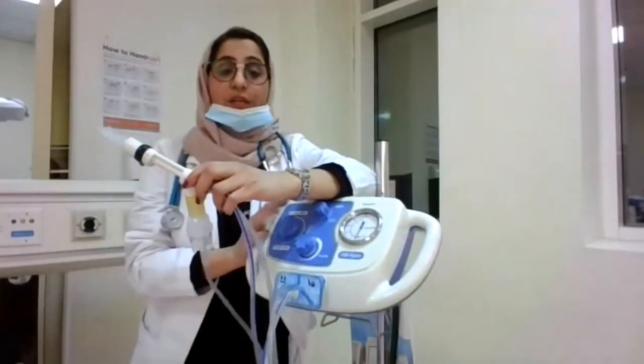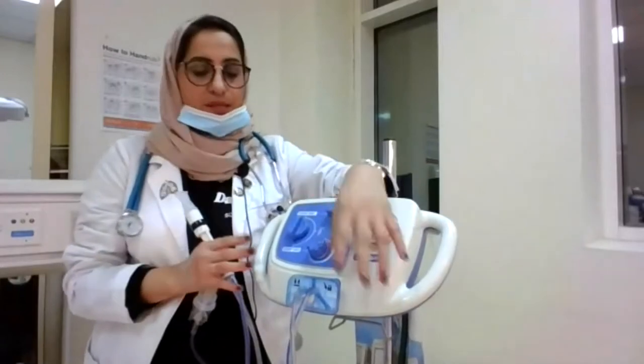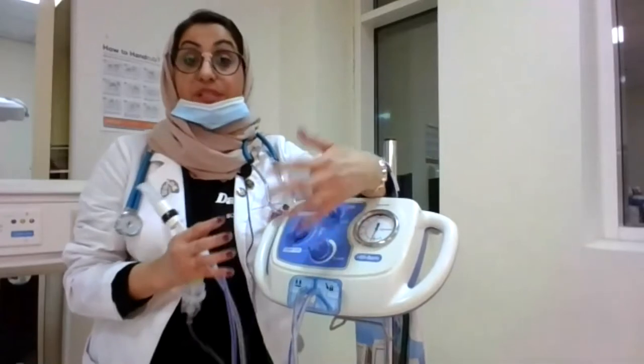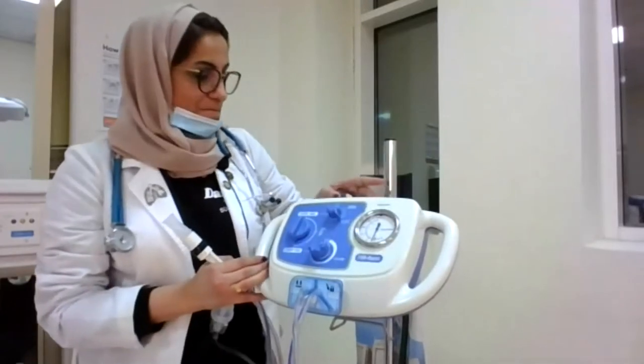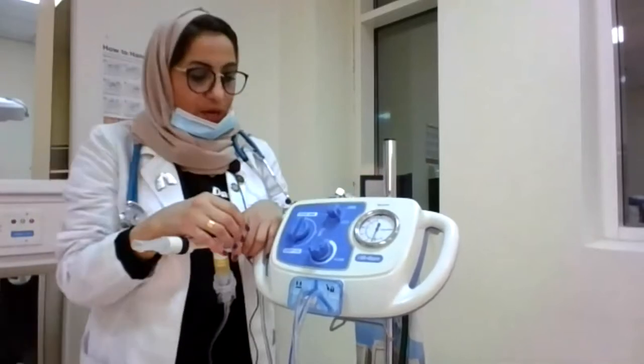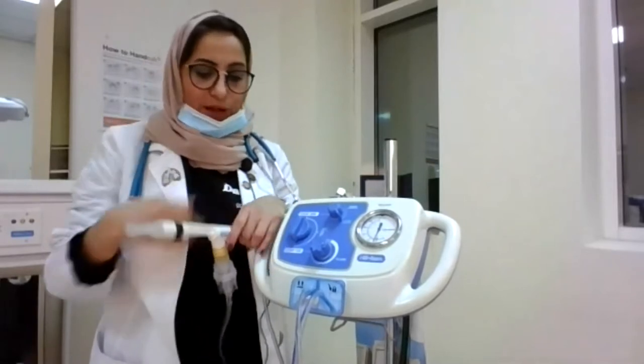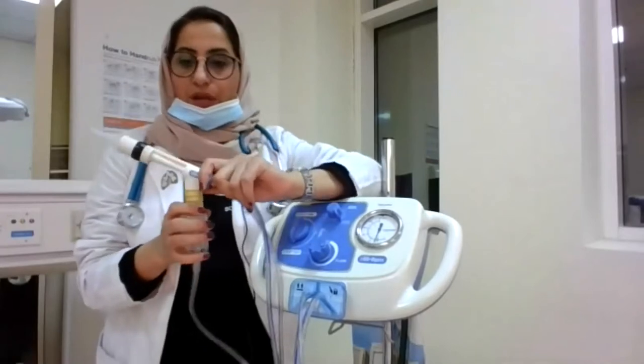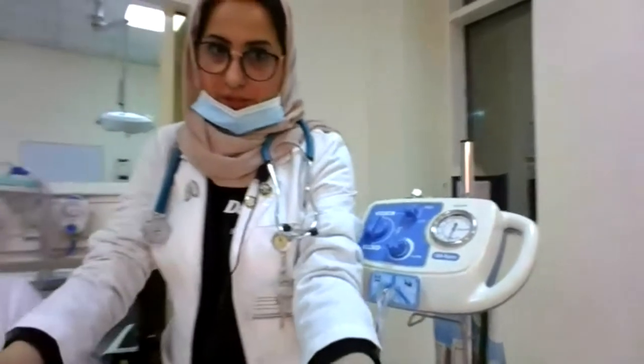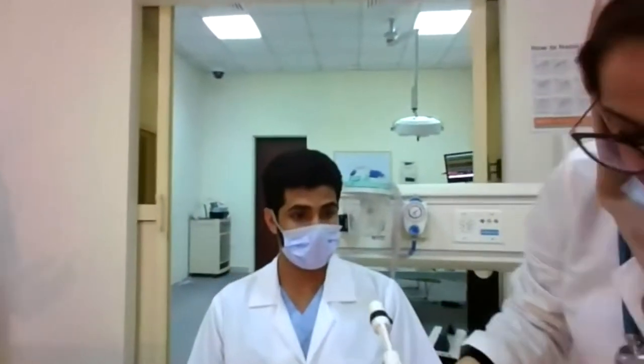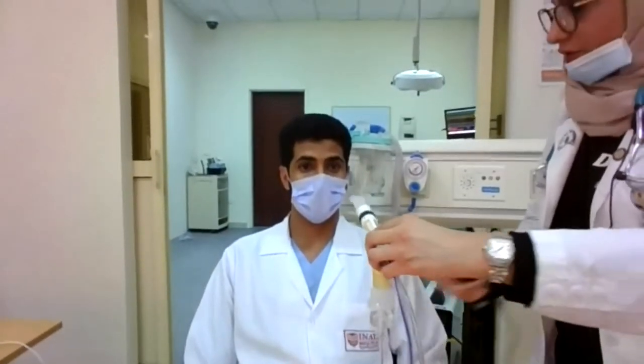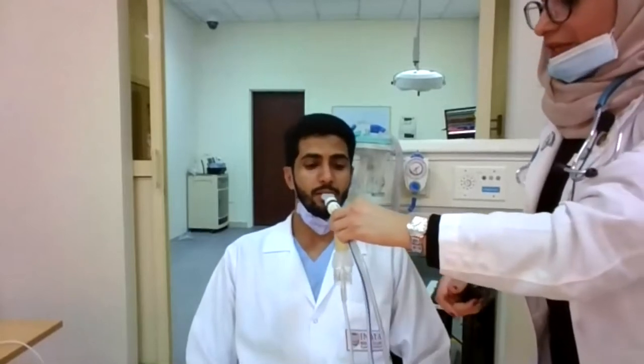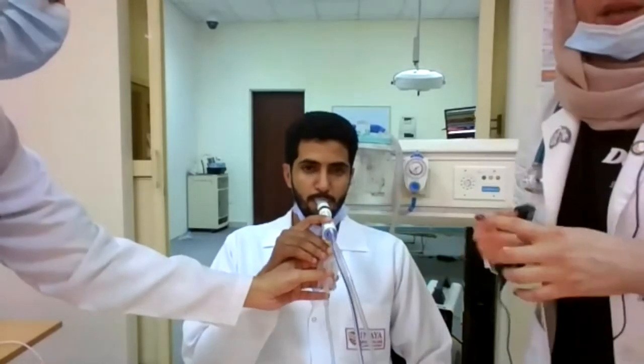Okay, we could use this treatment for 10-minute sessions, and we could prescribe it for patients 2 to 4 times a day. So we turn on the on and off button, and then we pick the mode that we want to provide. We pour the medication into the nebulizer, and if we're using the mouthpiece, we will just give it to the patient, who can start taking their treatment. It could be set for 10 minutes. It will be 2.5 minutes of aerosol and 2.5 minutes of lung expansion, and again, 2.5 minutes of aerosol and another 2.5 minutes of lung expansion until the whole 10-minute cycle is completed.